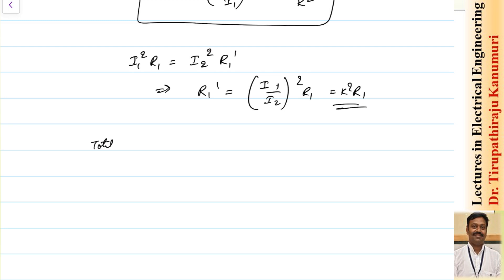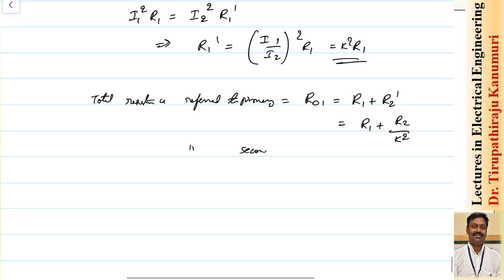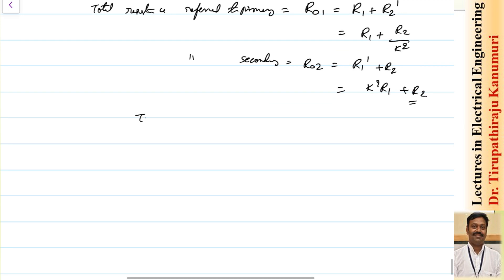The total resistance referred to the primary side is represented as R01. This will be equal to R1 plus R2 referred to the primary side, which is R2': R01 = R1 + R2/k². Similarly, R02 = k²R1 + R2 is the total resistance referred to the secondary side. Total copper losses can be calculated as I1²R01, which equals I2²R02.